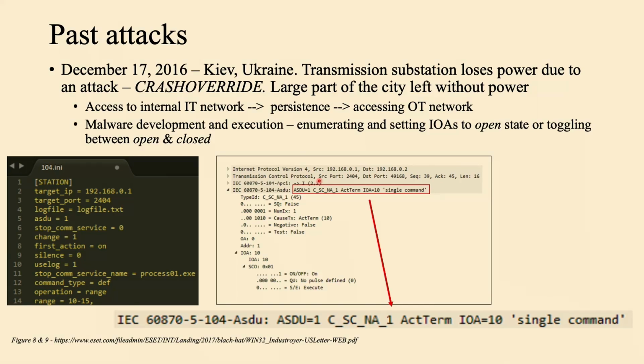And here I've cropped out the most important bit. You can see that the protocol used is the IEC 104, and it used this information object, which is called single command. And it used the IOA address of 10.